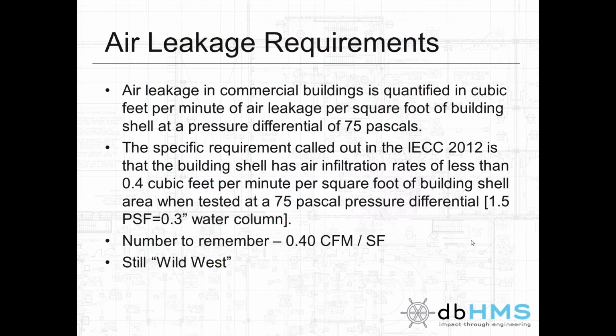The amount of air that leaks through the building enclosure tells us something about the infiltration rates that the HVAC system should be designed for. And it tells us something about how successful we were in commissioning the enclosure and getting it built. If we combine this with an infrared scan, provided there's a sufficient pressure or temperature differential, we can see where warm air is leaking into the building. And it's usually at a junction between two systems.